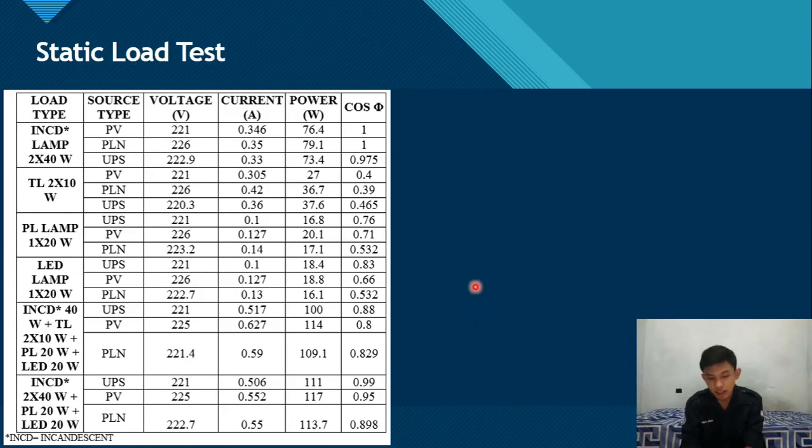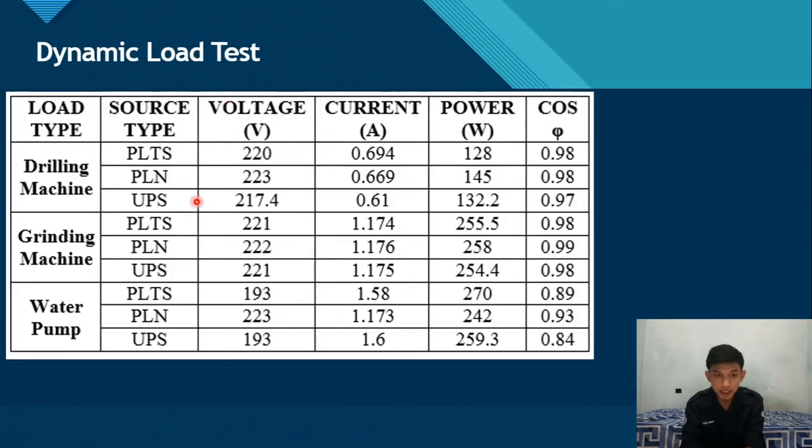Load tests have also been carried out using static load. The values of voltage, current, power, and cos phi are not much different, as well as when using a dynamic load test. The voltage, current, power, and cos phi are not much different.